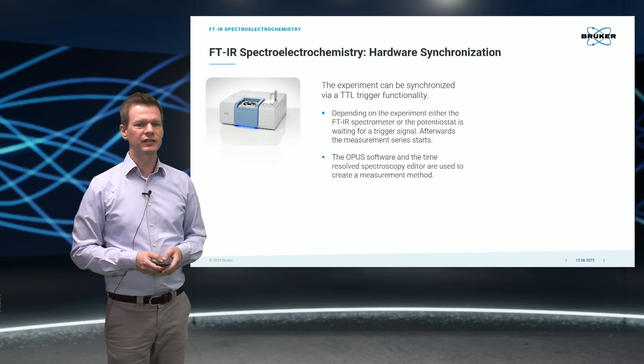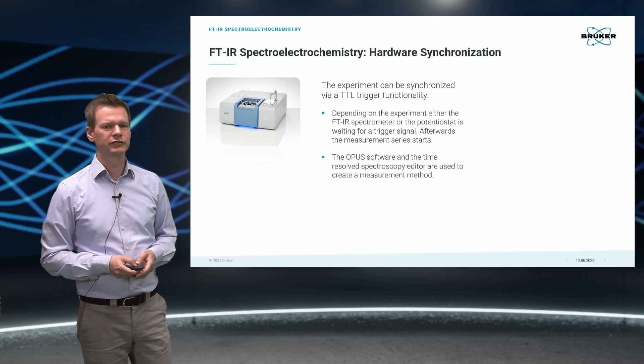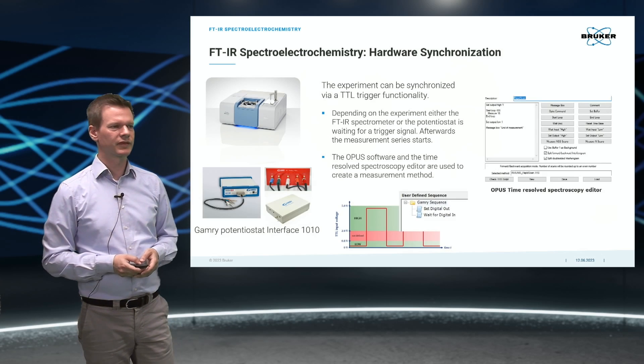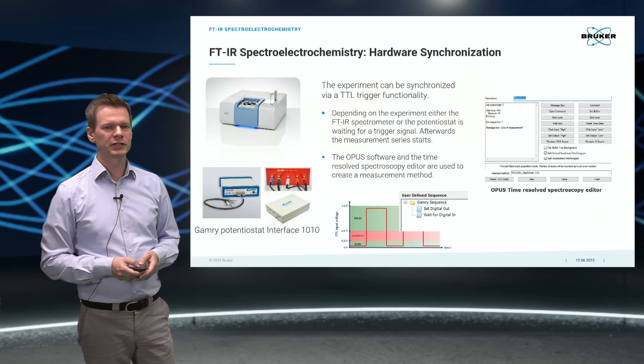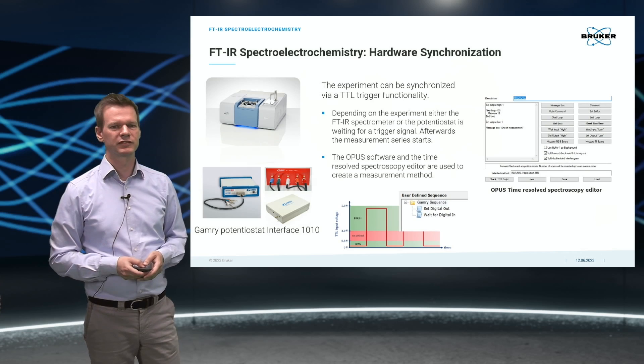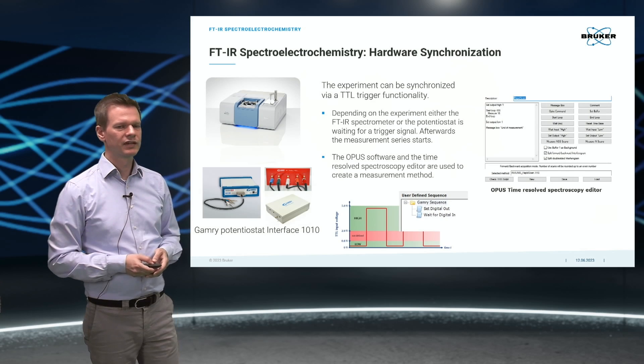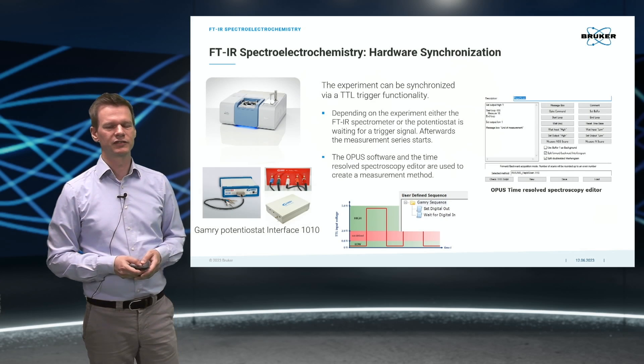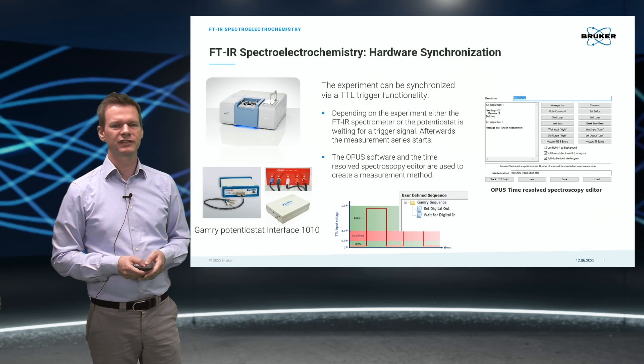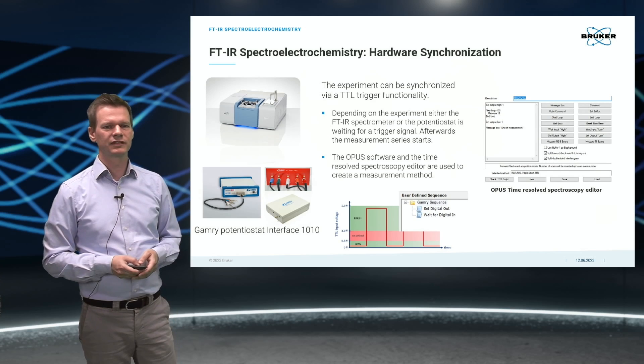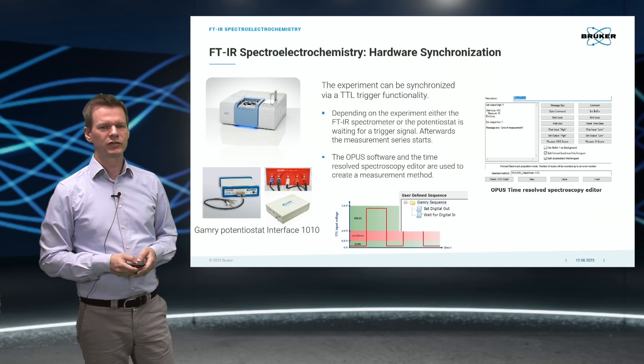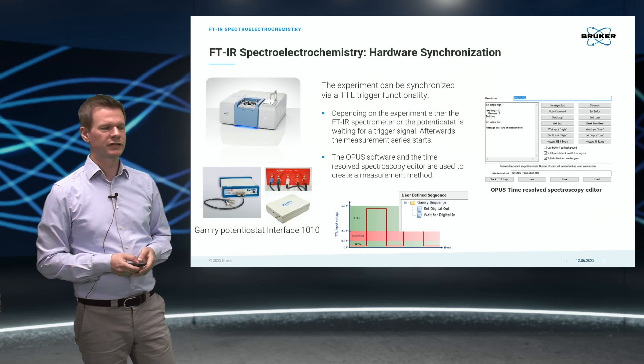A synchronized start of the combined experiment is essential to produce reliable data. Therefore, the FTIR spectrometer and the potentiostat can be synchronized with TTL trigger signals. This can be realized via the Gamry sequence wizard and the OPUS time-resolved spectroscopy editor. Both systems are able to send and to receive trigger signals. The synchronization of newly created methods can be easily tested with a demo cell, which is directly available with a potentiostat.